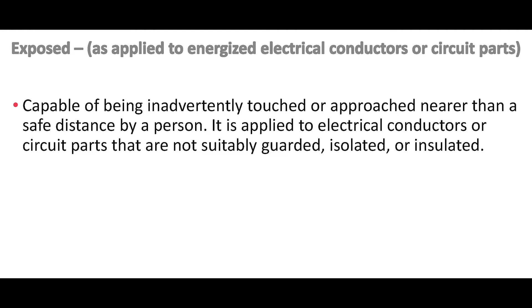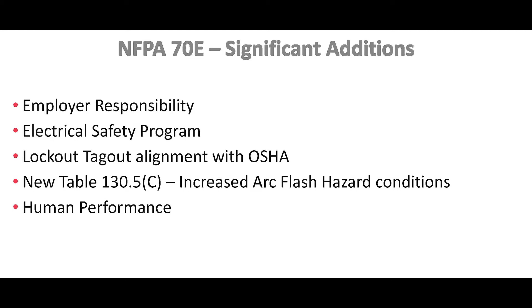If I pull this cover off and there's bare wires behind that cover, then it's exposed. We'll just leave it at that for now. So, some significant additions to NFPA 70E, which is indirectly what OSHA uses for their enforcement side. Employers' responsibilities: you must have an electrical safety program. Lockout, tagout was aligned with OSHA. And there's a new table that helps people determine when there is an increased chance of an arc flash. It gives you a matrix that tells you if you're doing this, then there's an increased chance. If you're doing this, but this, then there's not an increased chance. And then finally, one of the last topics I'm going to talk about is human performance.